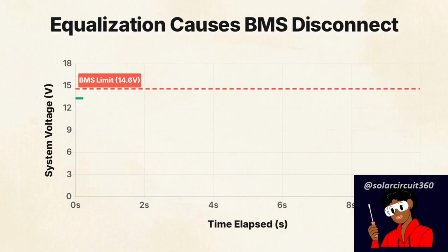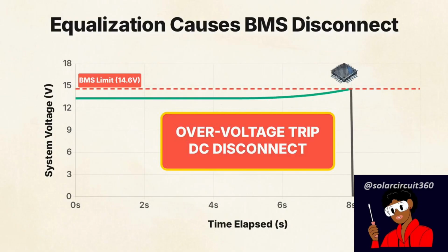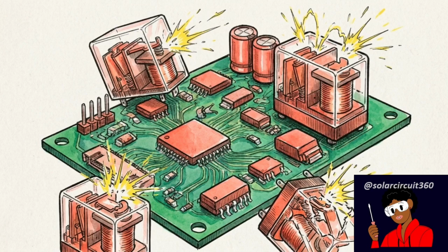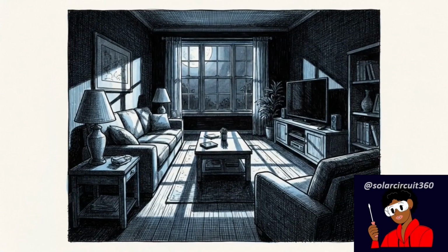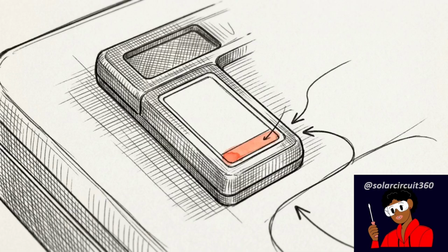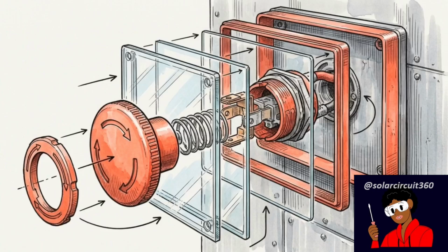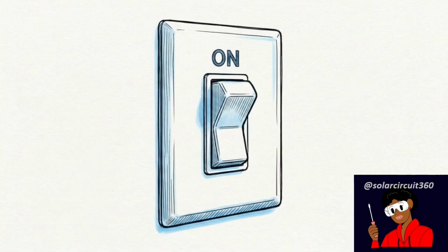Applying an equalization charge forces a massive voltage spike. As the lithium curve is pushed rapidly out of its safe voltage envelope, it triggers a sudden overvoltage protection fault. Carrying over legacy charging profiles forces the BMS to actively sever the connection to protect cells, causing the exact type of outage the system was built to prevent. That same logic applies to the bottom of the discharge cycle, where undervoltage risks occur. The battery's internal BMS is designed to be a last resort emergency brake. It is not meant to be used as a daily operational power switch.